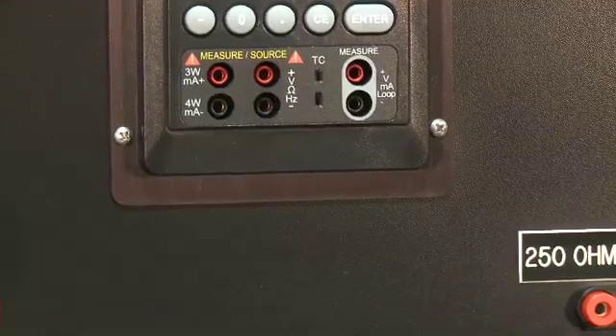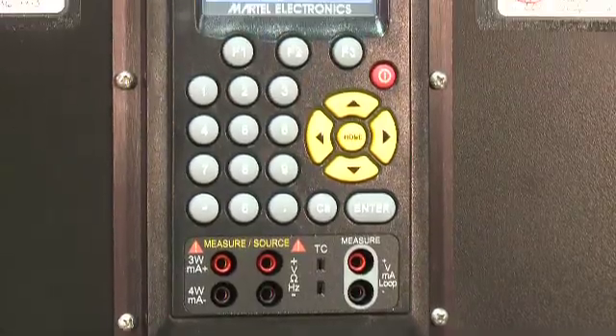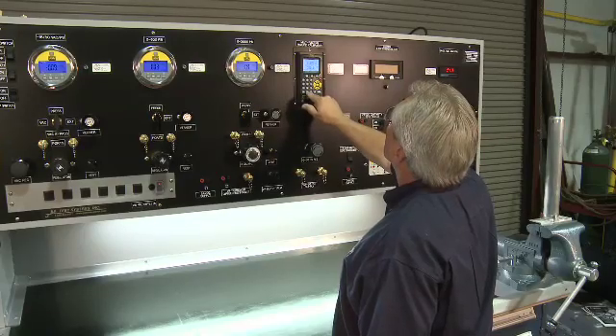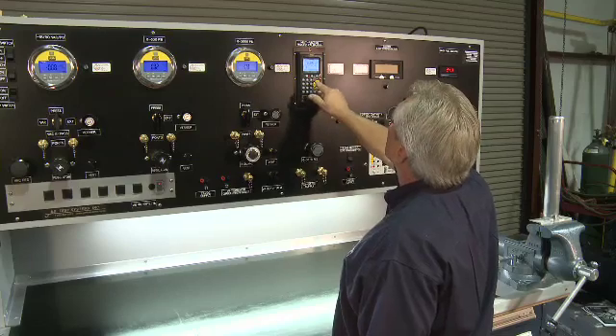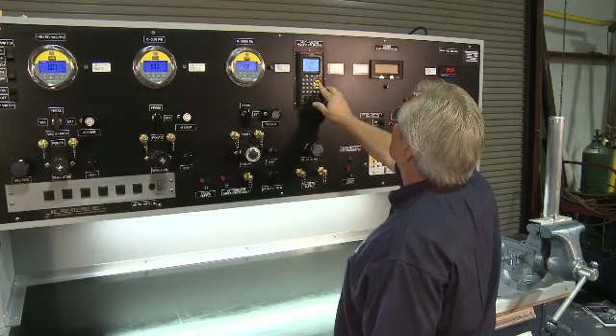The Martel MC-1210 features direct entry of custom RTD coefficients. All source modes can be programmed with dedicated set points to speed up calibration and linearity tests. This calibrator has the highest accuracy in its class, accurate to 0.015% of the reading.